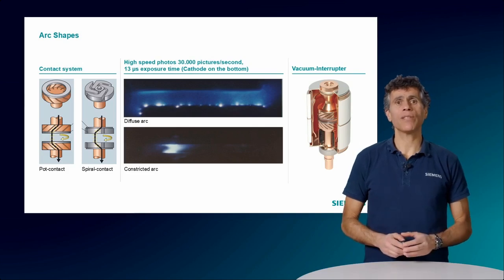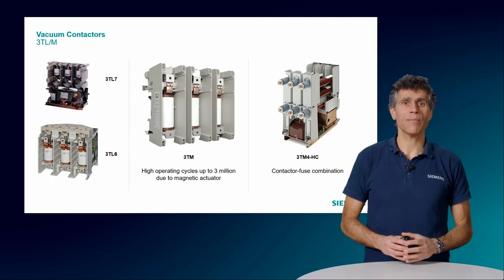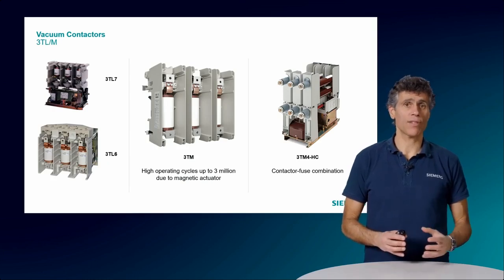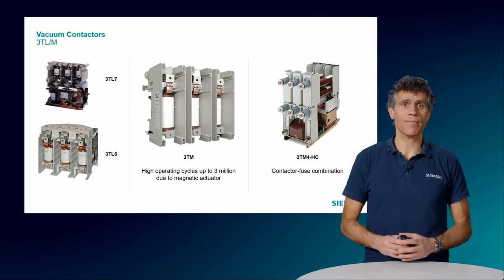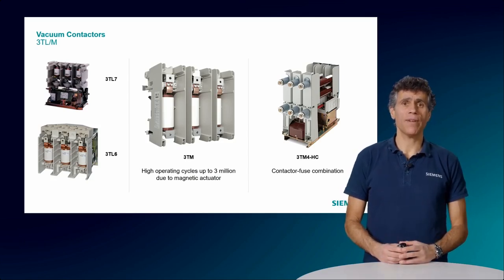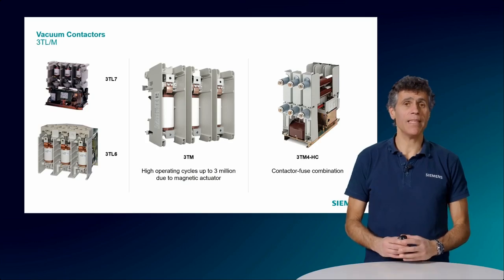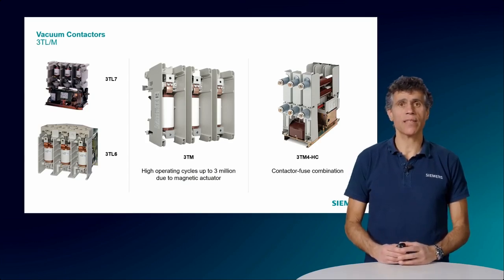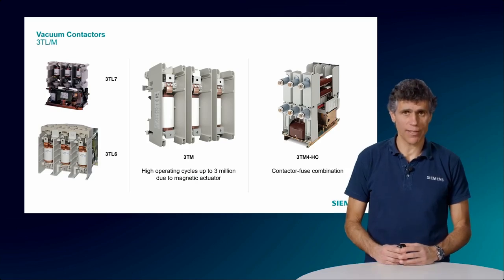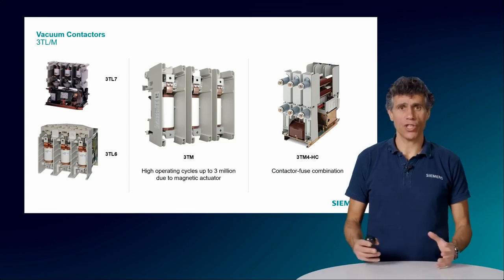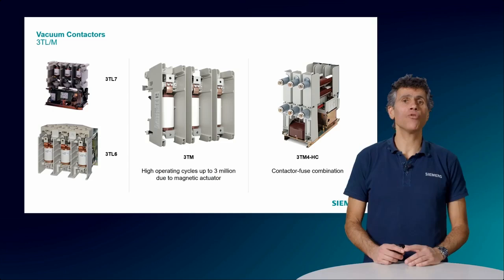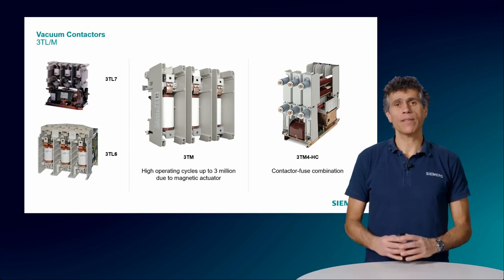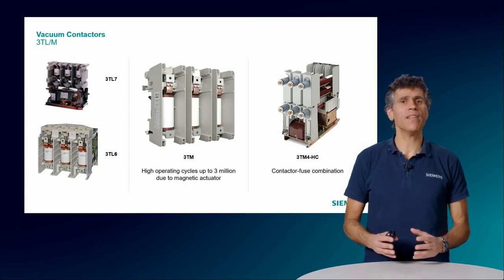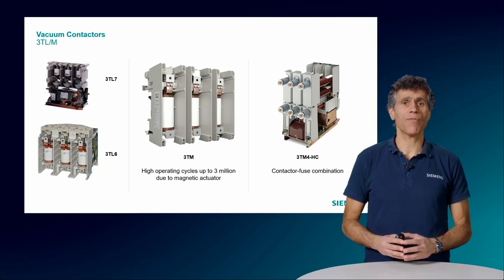Now that we understood how a circuit breaker works, it's easier to understand some different devices by comparing them to the circuit breaker. Let's firstly see the contactor. Its operating principles are very similar to those of a circuit breaker. The main difference is that, unlike circuit breakers, contactors are not meant to interrupt fault currents. Their main purpose is to switch on and off under normal operating conditions. Another big difference is that they are usually conceived to perform a much larger number of operations than a circuit breaker. Whereas a circuit breaker is built to perform something like 30,000 operations, some contactors can perform up to 3 million operation cycles.